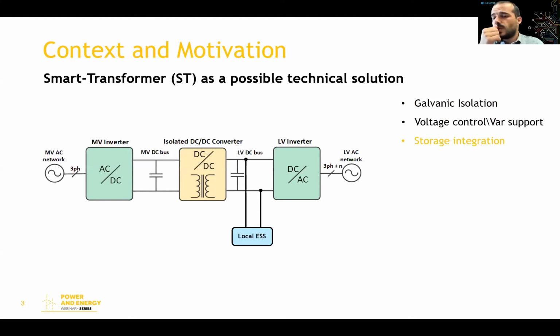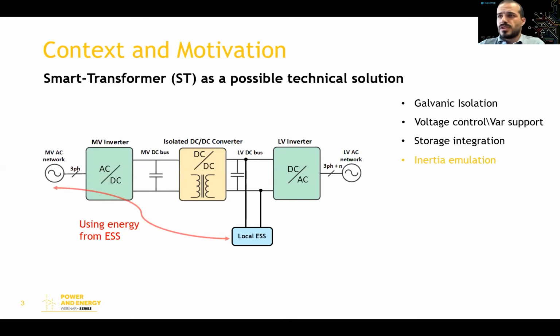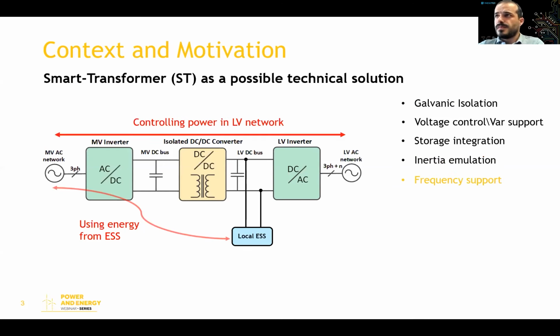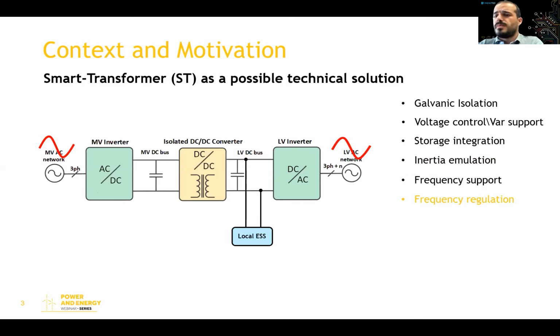It can also integrate storage and also use the same storage for inertia emulation using the energy available. It can also perform frequency support using the energy storage or controlling the power in the low voltage network. It can also perform independent frequency regulation. It can regulate the frequency in the low voltage network independently of the frequency in the upstream system. It can be useful to use this quantity as a regulation instrument.